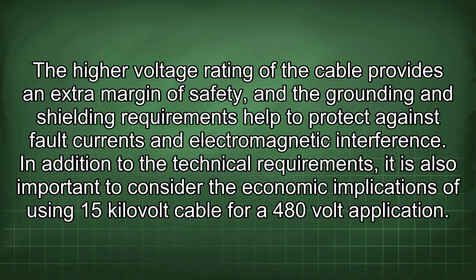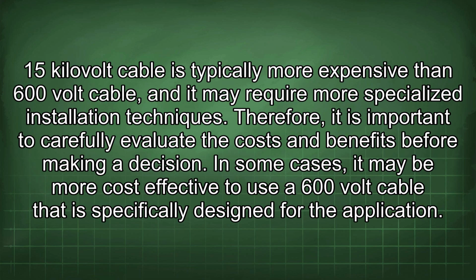In addition to the technical requirements, it is also important to consider the economic implications of using 15 kV cable for a 480 volt application. 15 kV cable is typically more expensive than 600 volt cable, and it may require more specialized installation techniques. Therefore, it is important to carefully evaluate the costs and benefits before making a decision.